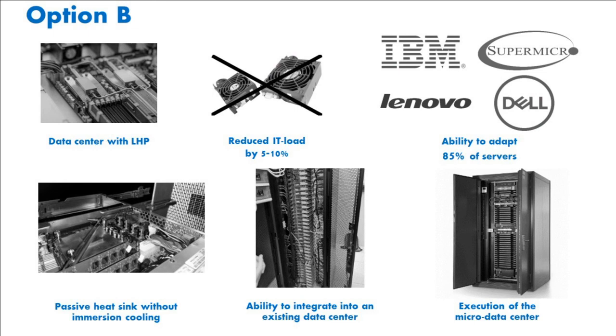With an innovative solution for server cooling from Tercon LHP, we reduce the energy consumption of the IT load by reducing the fans, due to a passive heat sink with a dry lock to the cooling rail at the end of the server rack. It is possible to use 85% of existing servers, among which IBM, Dell, Lenovo and Supermicro already use this technology. Integration is possible in water-cooled data centers as well as micro data center designs.